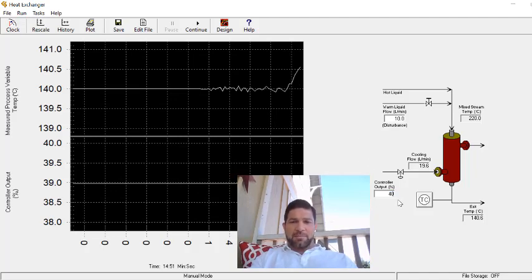Now I'm going to go ahead and step it up to 40. I started at 39, stepped down to 38. Now I'm going to step up to 40. So now I'm going to let this respond. And as soon as I see this value come back and cross the initial steady state value, I'm going to go ahead and step in the opposite direction. So now I'm going to step back to 38. Let the system change. Now it's gotten to the steady state value. So I'm going to go back up to 40.